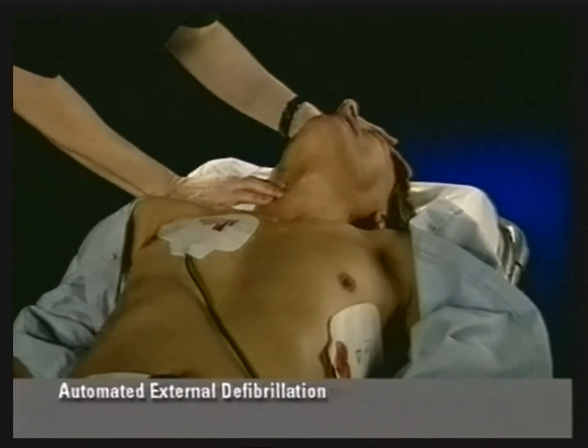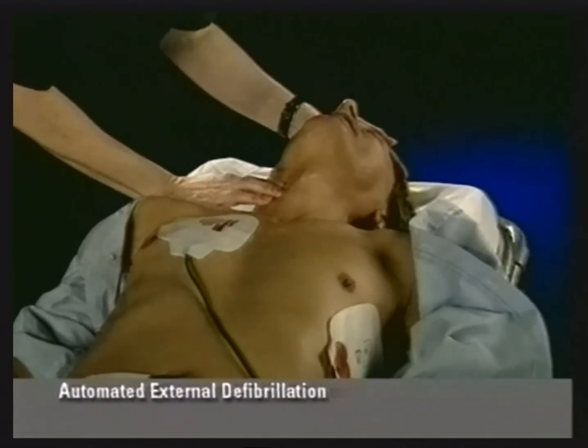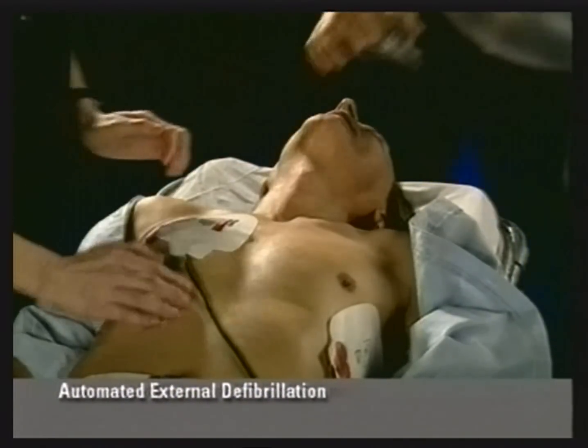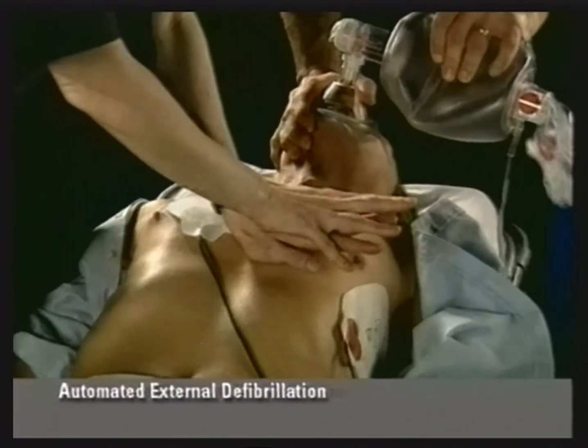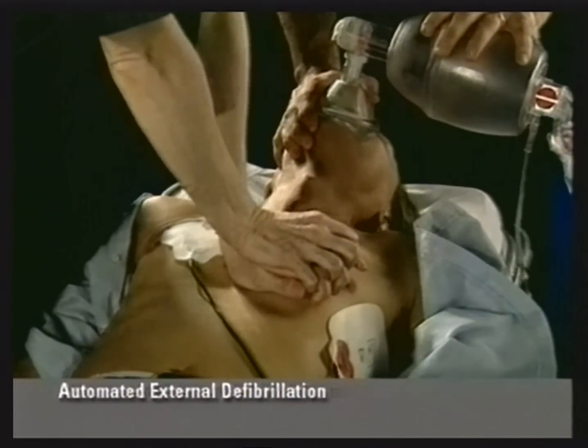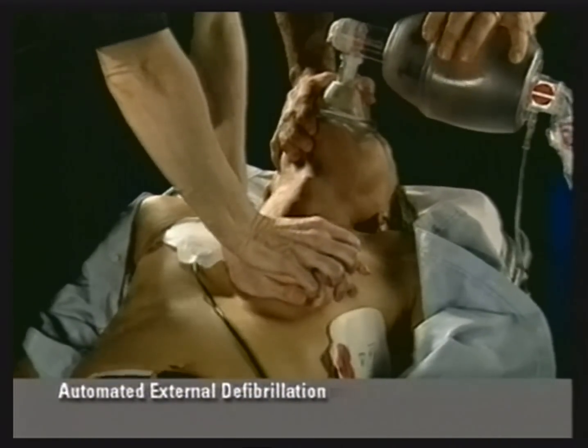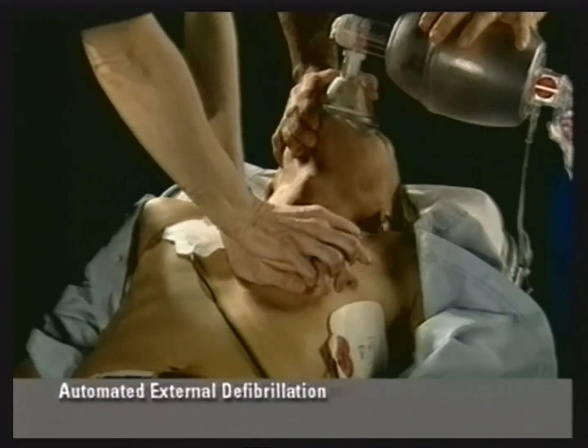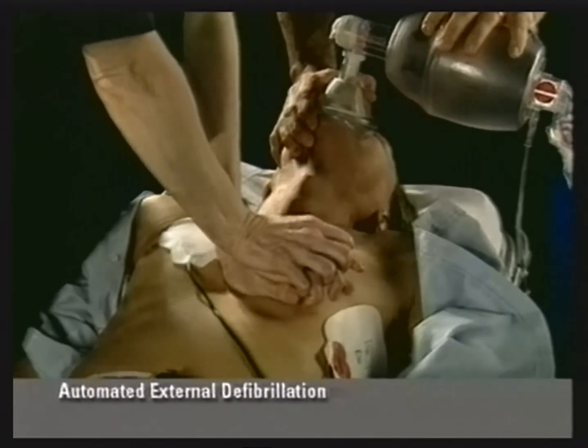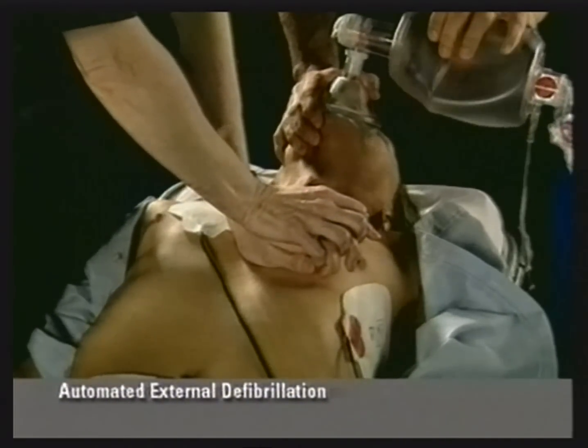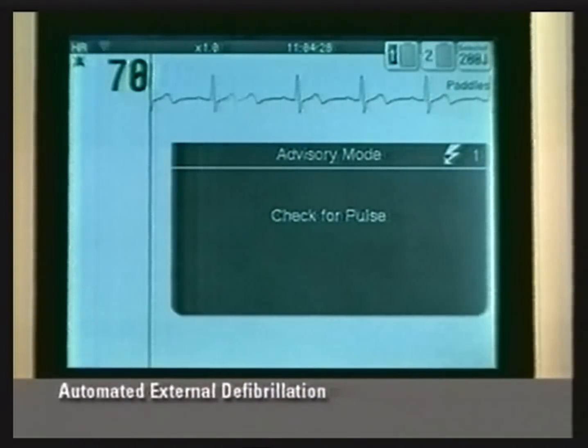If a non-shockable rhythm is detected, the defibrillator prompts, "No shock advised." Check for the presence of a carotid pulse. If there is no pulse, begin CPR. The defibrillator enters CPR time. The duration of CPR time can be adjusted to meet the needs of your local protocol. At the end of CPR time, the defibrillator prompts you to check for pulse.